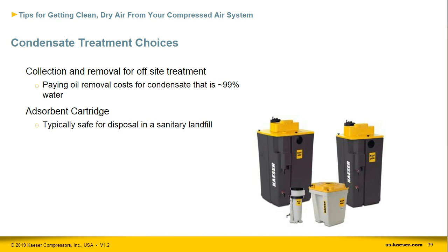A simple alternative is passing the condensate through an adsorbent oil-water separator. The oil collects on the cartridge and the water passes through, where it can be safely discharged to a wastewater drain. Once the cartridge is loaded up with oil, it can typically be disposed of in a sanitary landfill. This method typically has low initial cost, no energy cost, no oil waste disposal cost, and a moderate maintenance cost because of the replacement adsorbent cartridges.